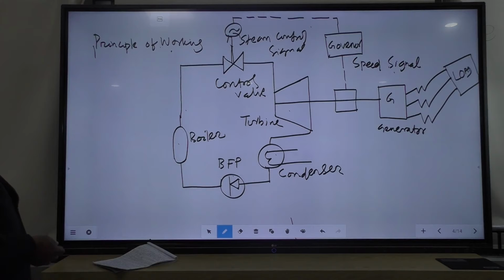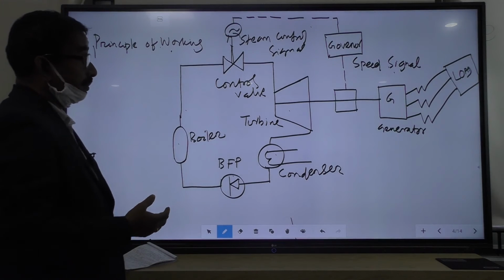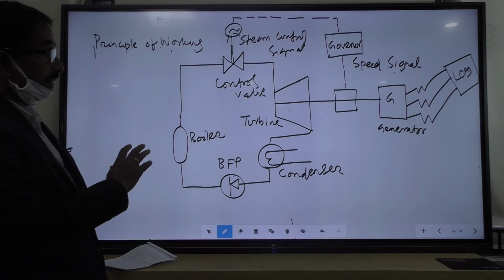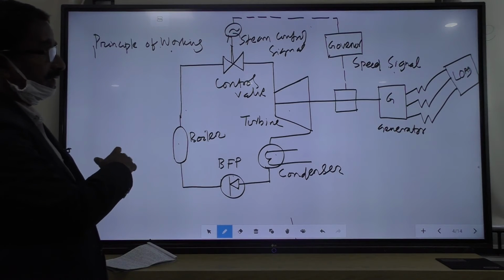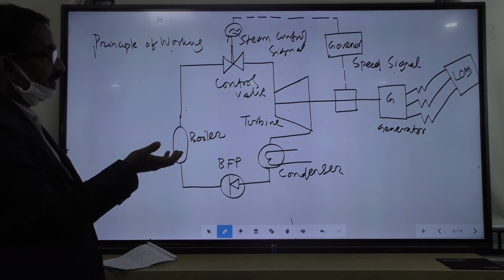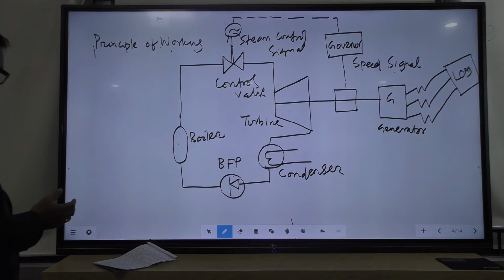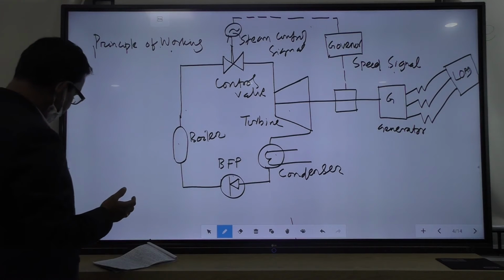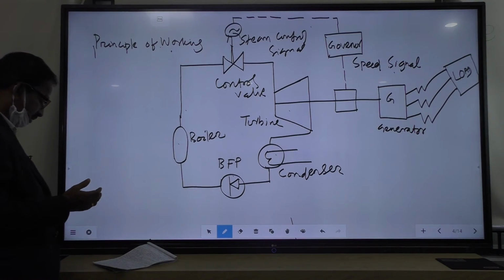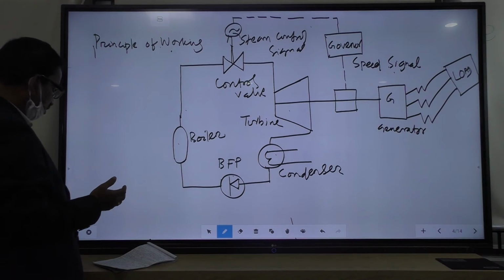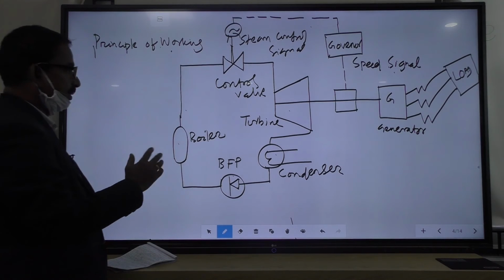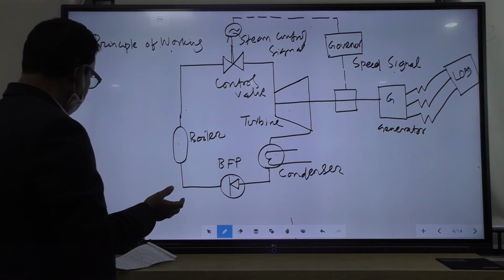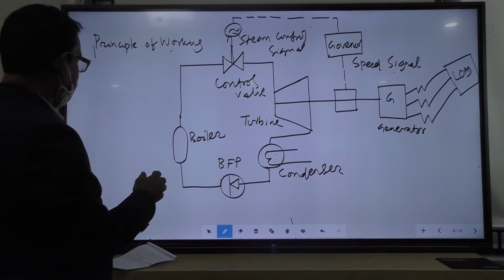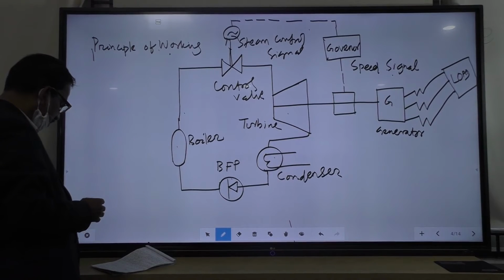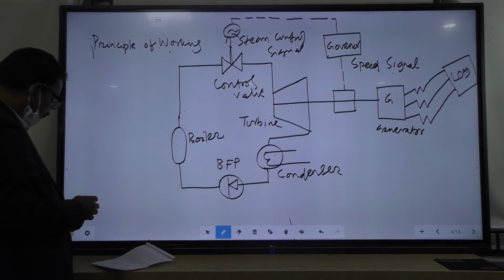And synchronize means the power we consume from the grid and the power produced by the plant should be equal, neither in excess nor less, that is synchronizing. It is the work of the governor. Number 2, to meet the load variation when running in parallel with the other machines. Whatever load variation happens, load less or more, that will be controlled by the governor. Number 3, to protect the machine from abnormal and emergency situation.